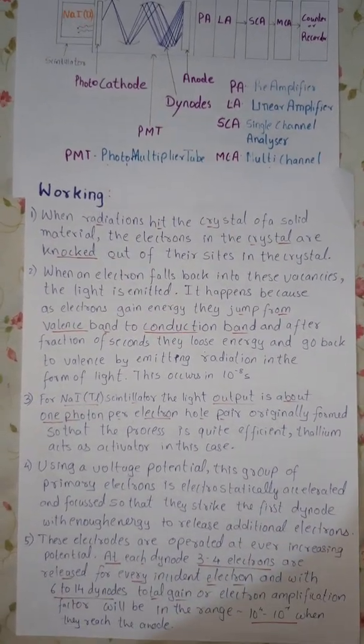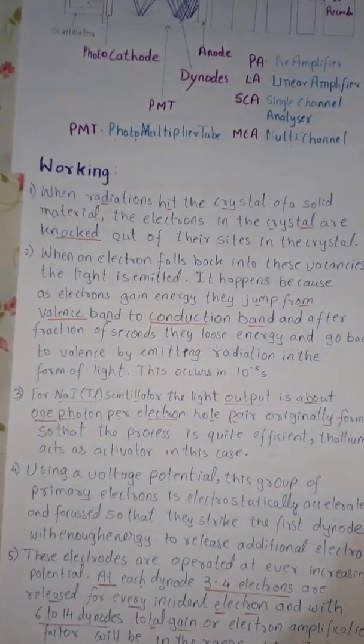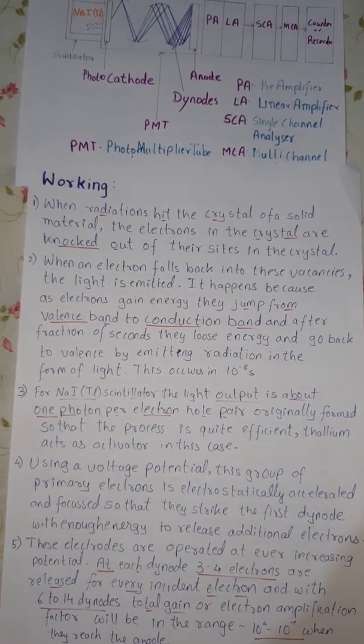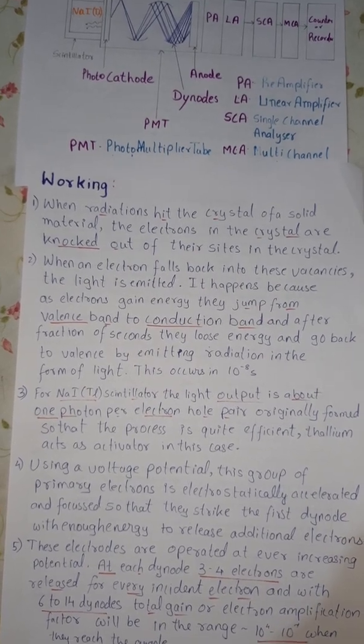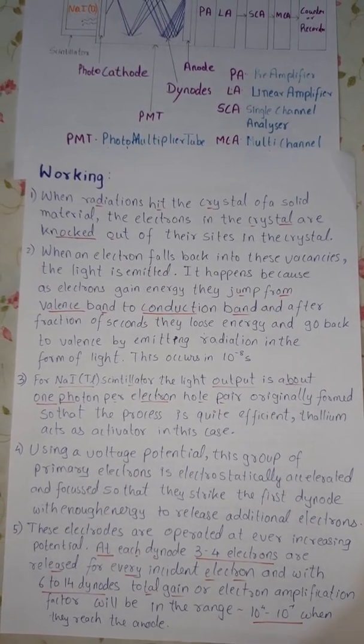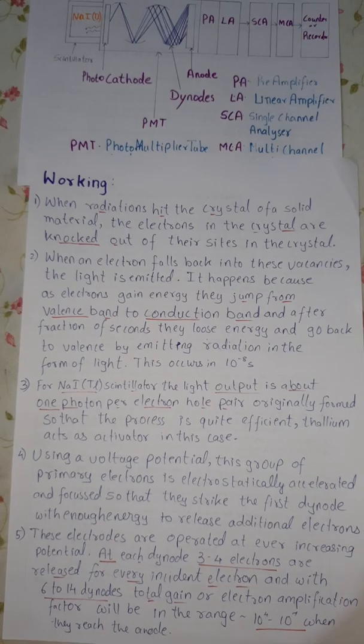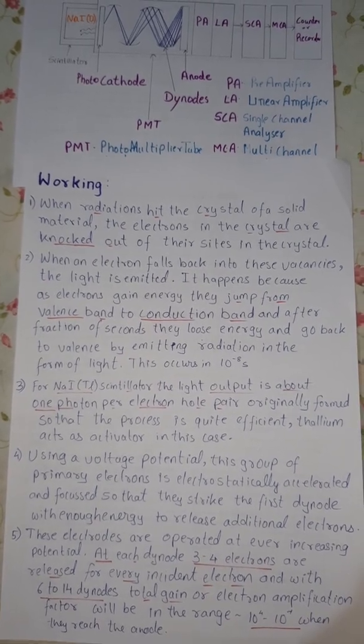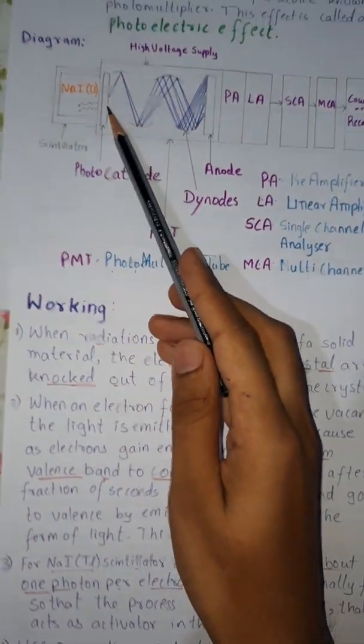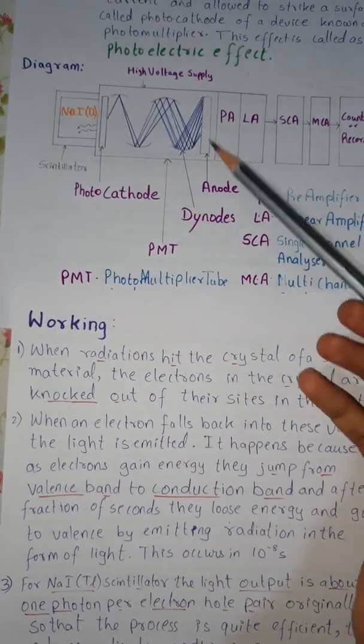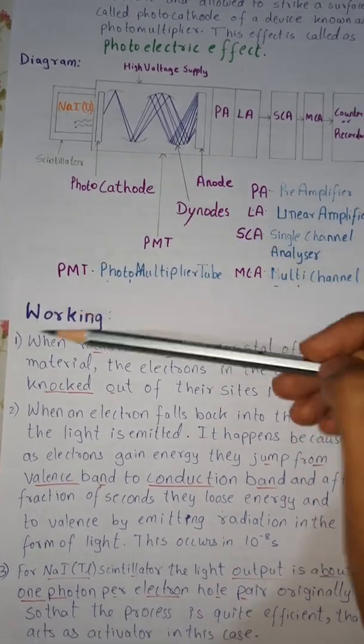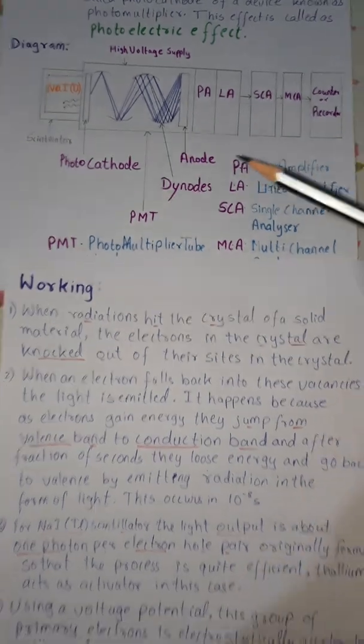For NaI(Tl) scintillator, the light output is about 1 photon per electron hole pair originally formed so that the process is quite efficient. Here the thallium acts as activator. Using a voltage potential, this group of primary electrons is electrostatically accelerated and focused so that they strike the first dynode with enough energy to release additional electrons. When the electrons are excited, they hit at the dynode and there are secondary electrons generated. These secondary electrons again hit the next dynode and again there are secondary electrons produced and hence they multiply in this manner.